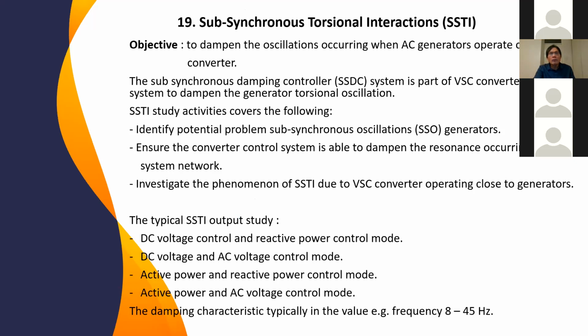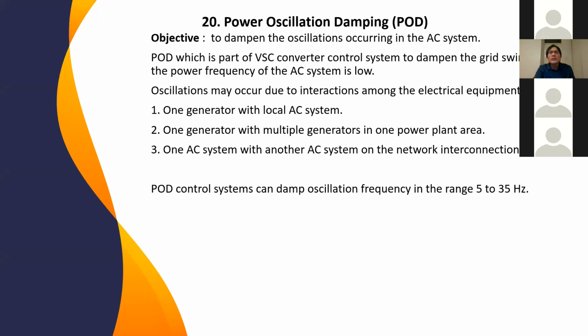The subsynchronous damping controller system, which is part of the VSC controller, dampens the generator torsional oscillation, which can be created by the converter station or an AC generator operating close to the converter station. POD, the objective is to dampen oscillation occurring in the AC substation or AC system, which can be between a generator and the local AC system or between one generator and another generator in the power plant area. POD, which is part of the VSC converter control system, dampens the grid swing when the power frequency of the AC system is low.